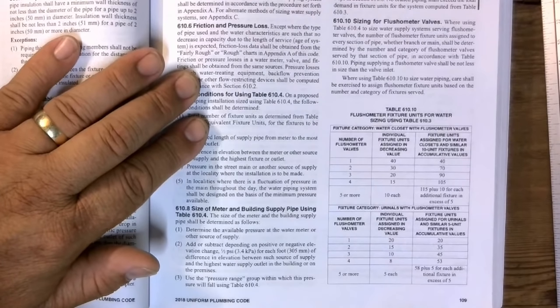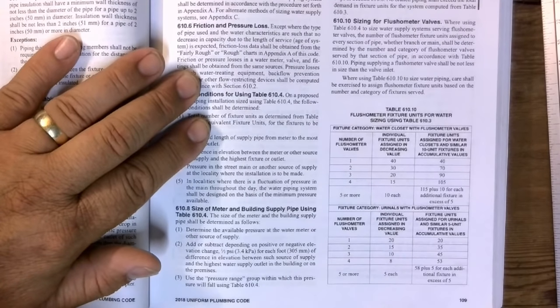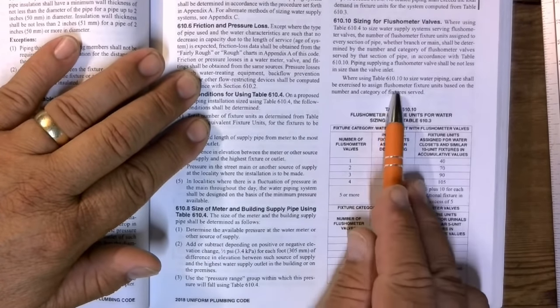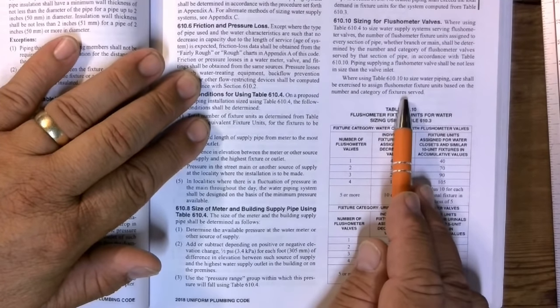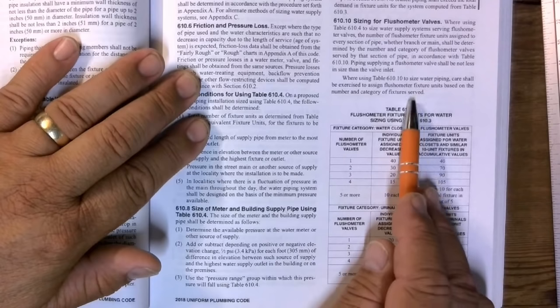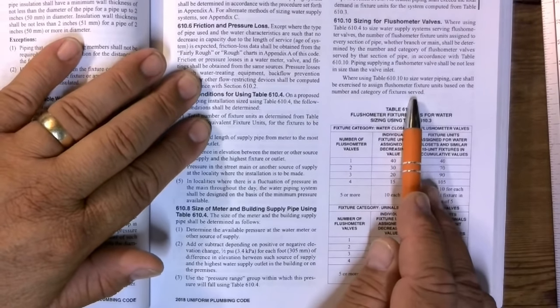The number of flushometer fixture units assigned to every section of pipe, whether branch or main, shall be determined by the number and category of flushometer valves served by that section of pipe, in accordance with table 610.10. The piping supplying a flushometer valve shall be not less in size than the valve inlet. On a water closet, it's a one inch line. On a urinal, it's a 3/4 line. So we're using table 610.10 to size the water piping. Care shall be exercised to assign the flushometer fixture units based on the number and category of fixtures being served.